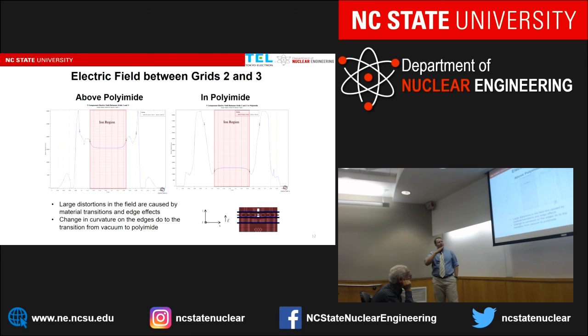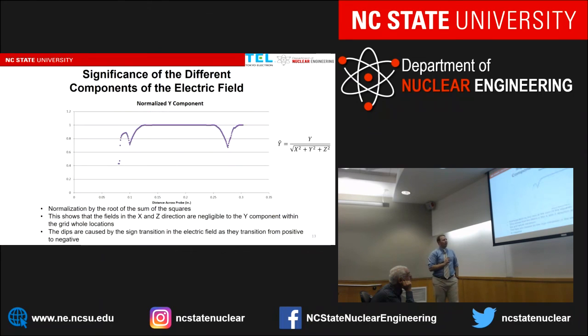You don't want the ions to experience a different electric field at different portions in the probe, because that's going to affect your measurement. So we want to try to basically make this as flat as possible. And since it changes from concave up to concave down, we thought changing those geometric parameters could possibly make it completely uniform.